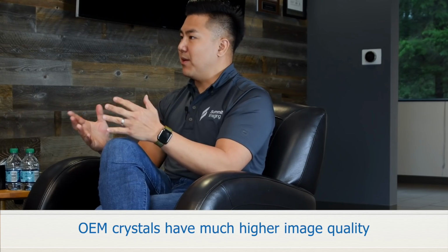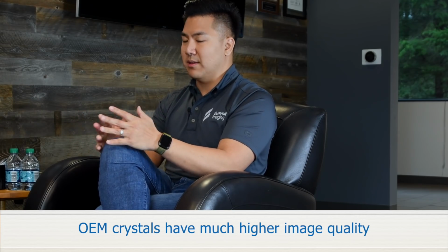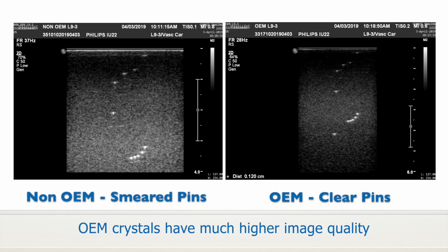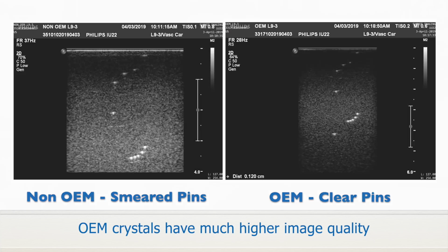So I think what we found out during that scan was that the clarity and the resolution of the counterfeit parts that have been installed by another facility somewhere else, we have no idea where, degraded the image quality to where there was a significant difference, to where professionals like you could instantaneously tell by simply putting a probe onto a phantom. And so that's kind of what we've been learning with Carolyn over the years, and now Matthew's a part of the team on really trying to tackle this issue to improve patient care.